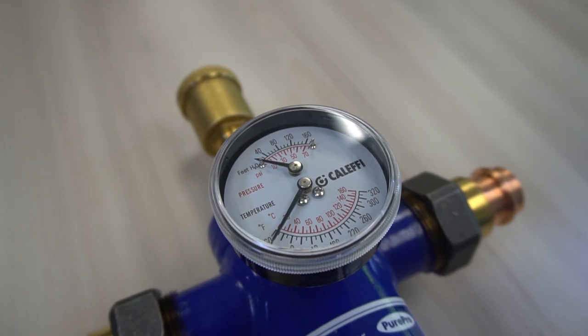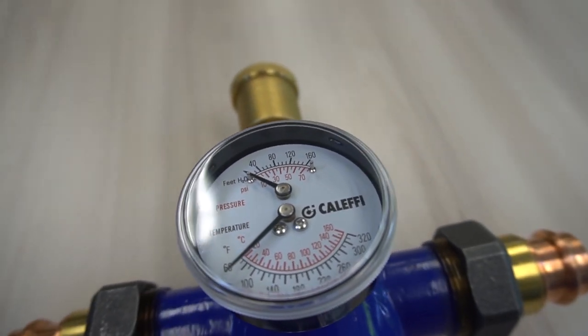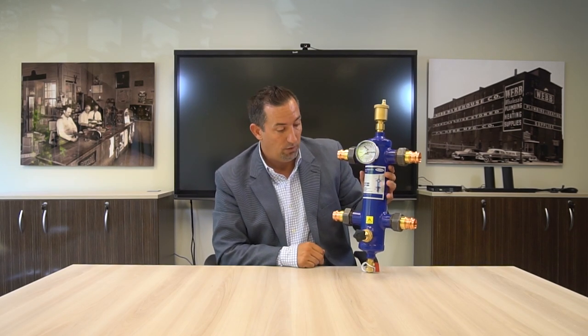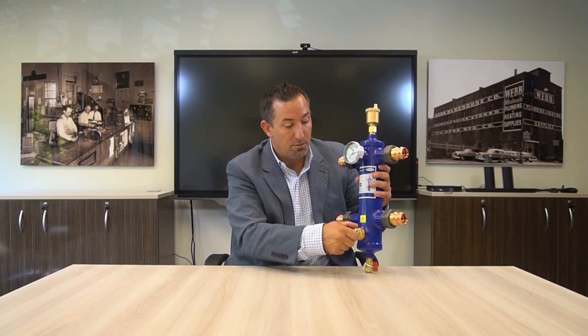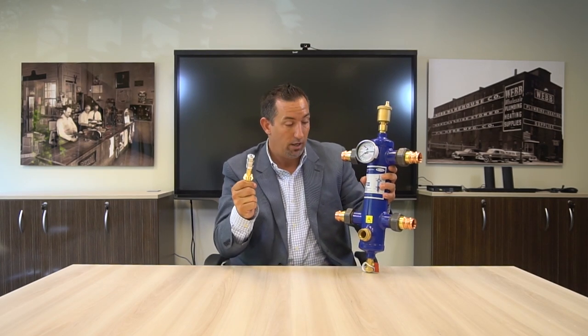Another thing I want to talk about is this Tridicator right here. You're going to get temperature and pressure readings on the Tridicator right in front, right on the system. So again, hydraulic separation, primary secondary piping is done correctly, first time, every time. Stainless steel coalescing air elimination, not just getting rid of the big bubbles, but getting rid of all those micro bubbles too. Very important. Dirt elimination, ferrous material, magnetic removal, okay? Going to protect the heat exchanger, make sure that boiler lasts a very long time, and also protect a lot of the system components around it.